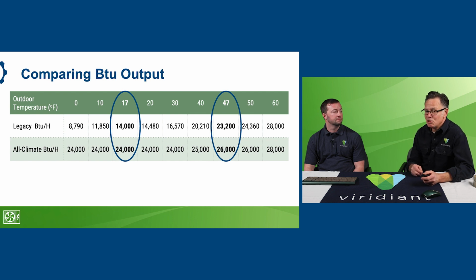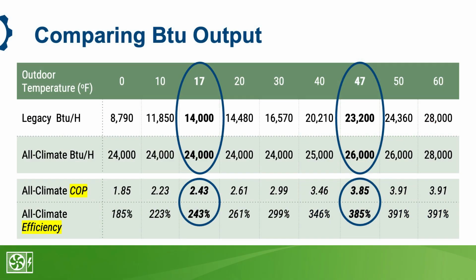But look at the all-climate heat pump. At 17 degrees ambient temperature, which in the southeastern US is the design temperature we're after at this climate, it's still producing 24,000 BTUs. It's still a 2-ton heat pump. So if that's what the home needed, we're delivering.